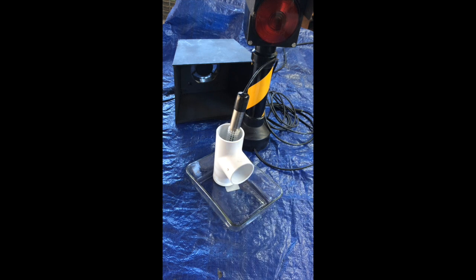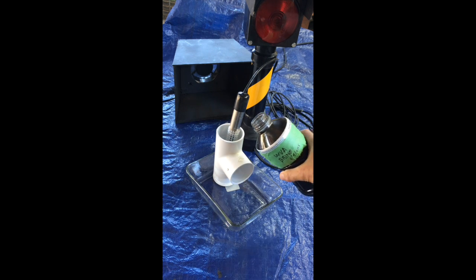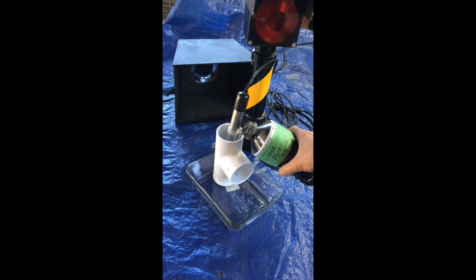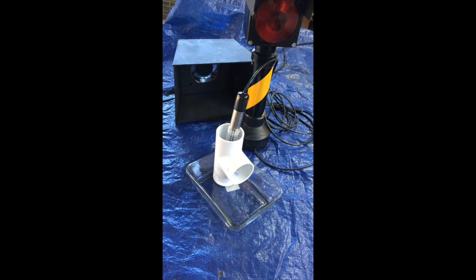So the indication instrument for this particular test is the flasher unit. You can see it in the upper right hand corner of the video, and it should start flashing red if and when the brine is detected. So I'm going to slowly add the brine and we'll see what happens. Okay, as you can see, we had almost immediate detection.